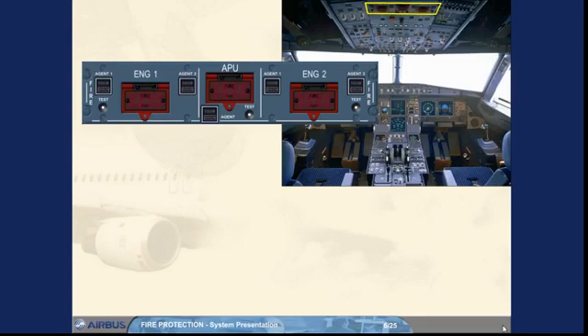The guarded fire push buttons give a fire indication and enable, when released out, the related system to be isolated, and the agent push buttons to be active. Note, each fire indication has 2 sets of 4 red bulbs. Each set is triggered by a fire detection loop.